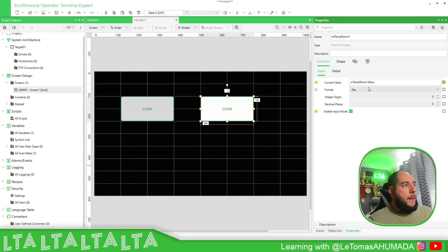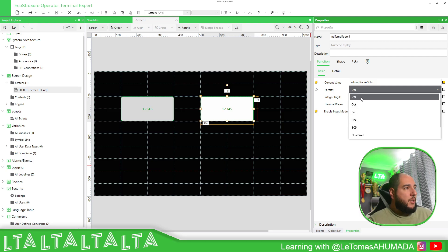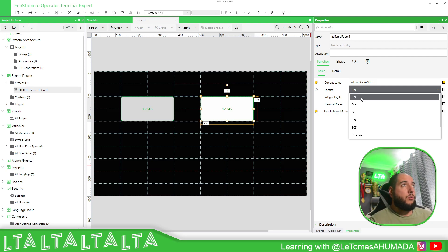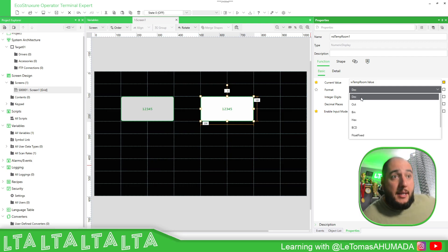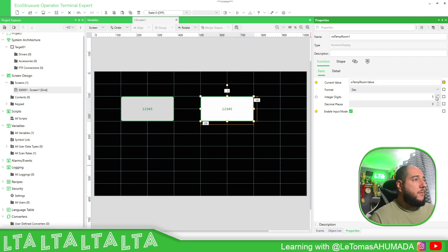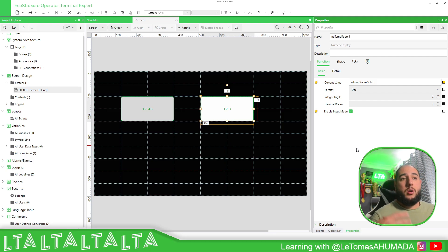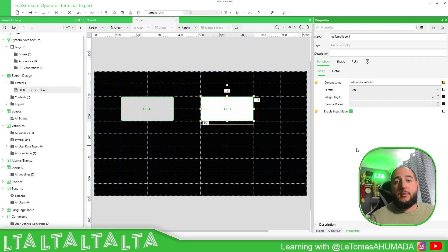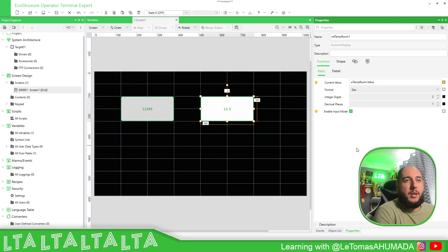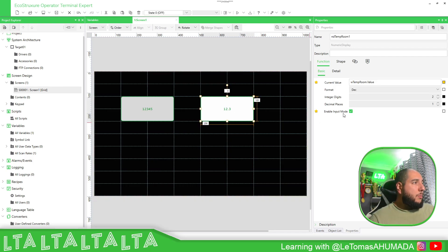Now for the one I'm selecting for changing the temperature, I need to enable the input. Then we need to select the format — how the HMI is going to read the value, or how you want to visualize it on the display. Here you set the integer and decimal portions. For example, if you're using words for temperature and you have 22.5 degrees, it usually goes to 225 internally, which isn't good to show on the HMI, so you put the decimal in the right place to display it nicely.